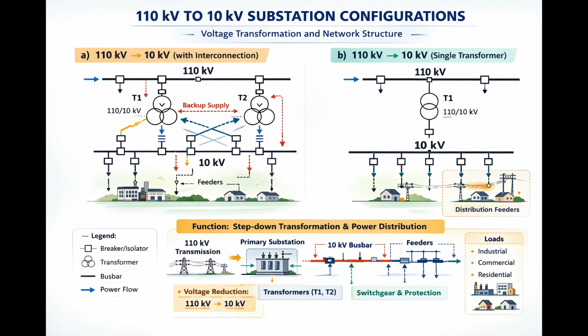The choice between the structures depends on load density. In dense centers with hospitals and data centers, interconnected 10 kV systems are justified. In rural regions with dispersed load, independent radial feeders are economically justified. As an engineer, you must evaluate not only technical performance but also economic impact. High reliability always increases cost.